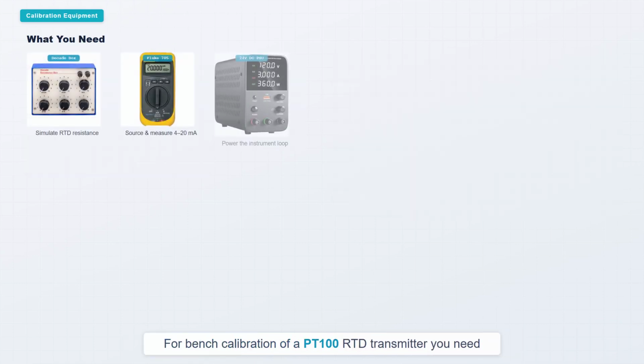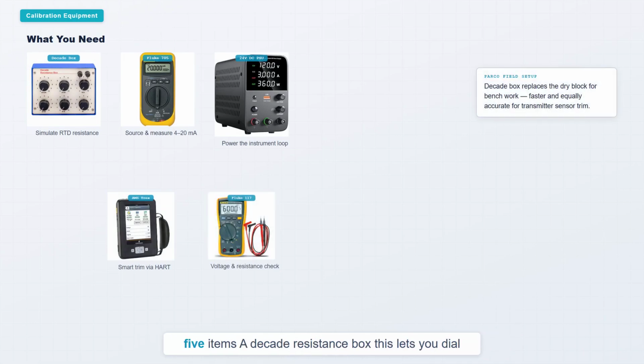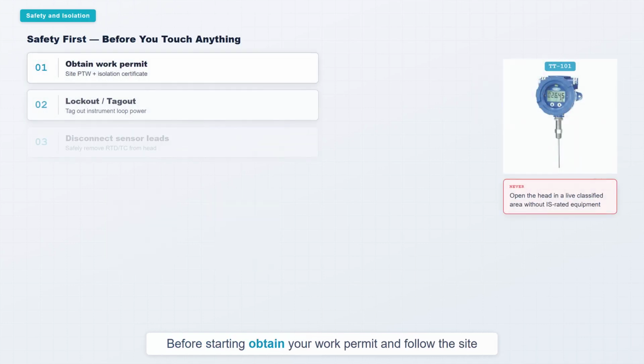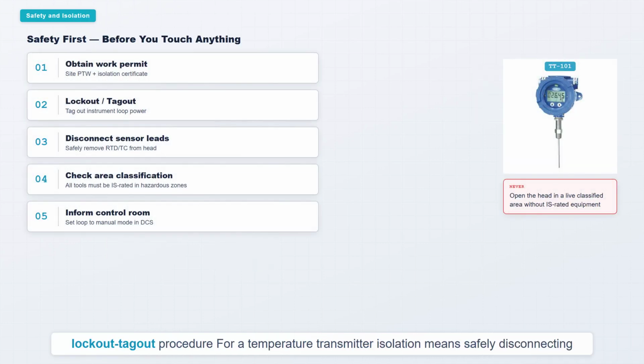For bench calibration of a PT100 RTD transmitter, you need 5 items. A decade resistance box. This lets you dial any resistance precisely, simulating the RTD at a known temperature. A loop calibrator like the Fluke 705. This sources and measures the 4 to 20 milliamp signal. A 24-volt DC power supply for the instrument loop. A digital multimeter for voltage and resistance checks. And for smart HART transmitters, the AMS Trex communicator, which connects across the loop and lets you run all trim functions from its touchscreen.